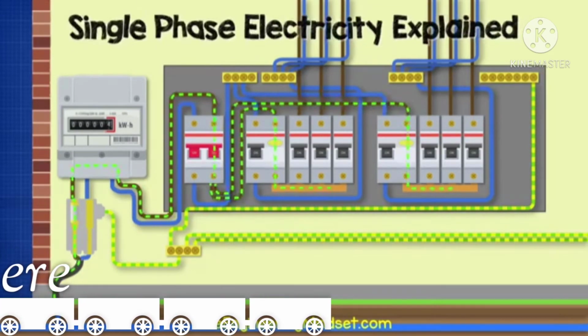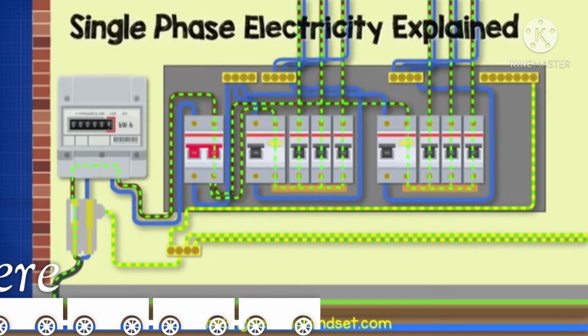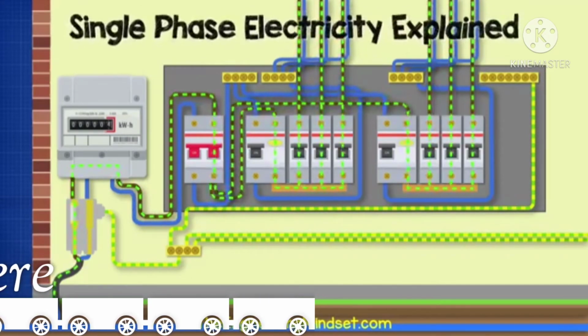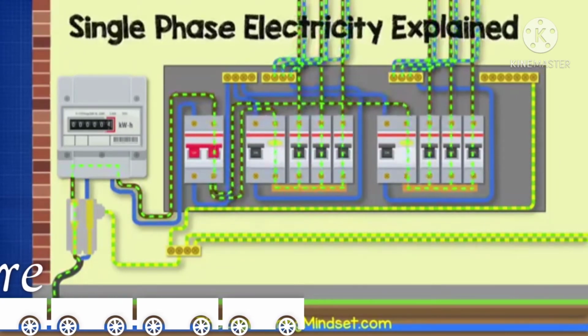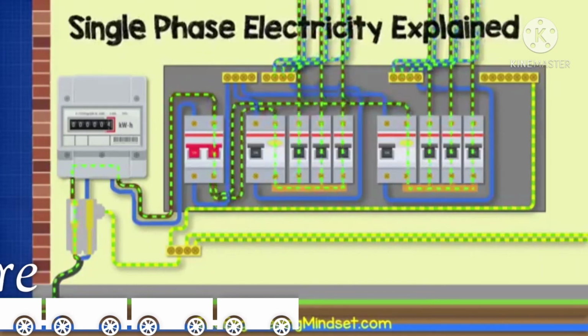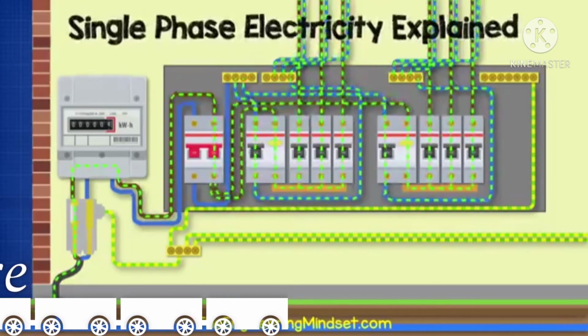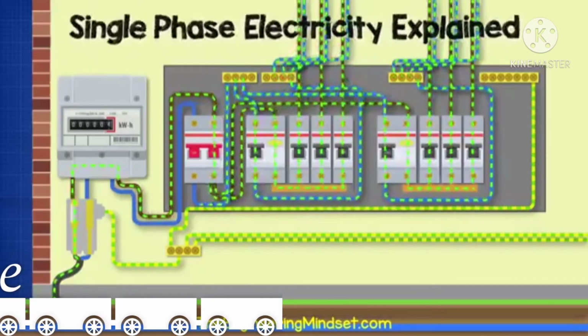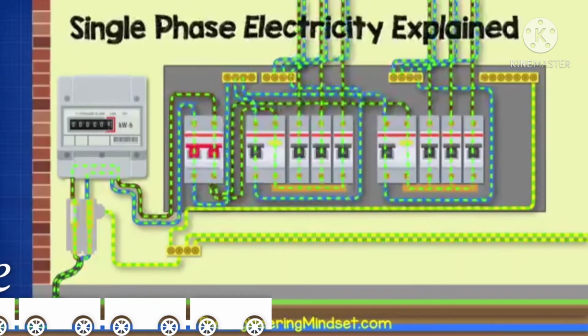From the main switch it flows through the RCD, along the bus bar and into the MCB. It then flows up around the MCB separated circuits. The electricity can then come back via the neutral lines and into the neutral blocks. It then flows through the RCD and back into the main block. From there back into the main switch and then the electricity meter. It will then pass through the service head and the fuse and back into the neutral line of the main distribution cables.